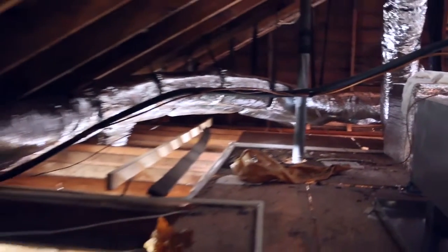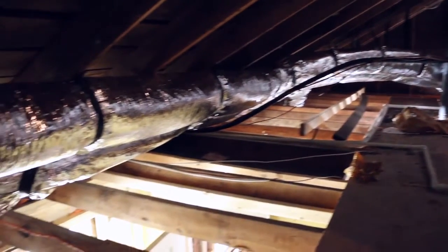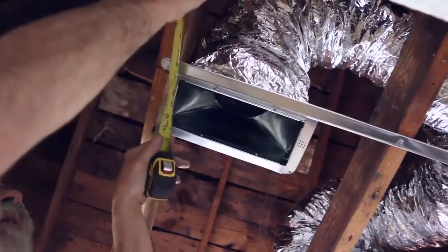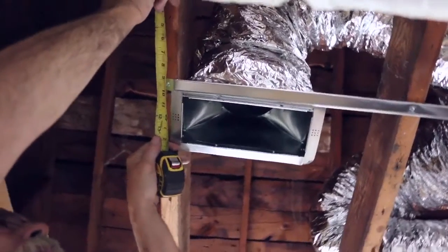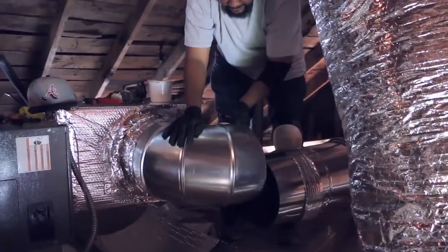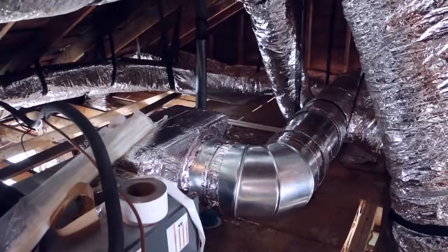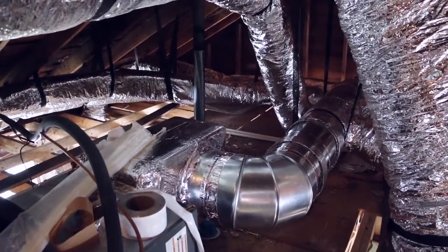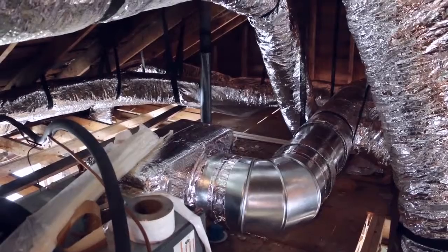Proper duct design involves having nice clean straight lines for your ductwork with minimal turns and bends, definitely no pinches. Wherever you have a takeoff or a Y or a split or a turn, you want to use hard metal pipe that minimizes turbulence and air friction.